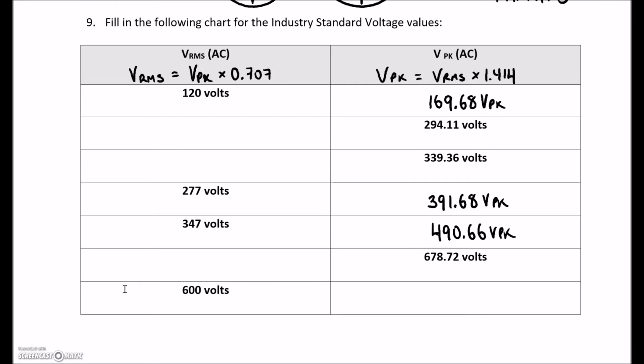So, again, if you are working live, you're a donkey. If you have no choice, and you're working live, then use the appropriate PPE. If you're working for a donkey who continuously makes you work live, then go find somebody else to work for. Right? 347 is a disgusting voltage. You're actually working on 490 volts peak.